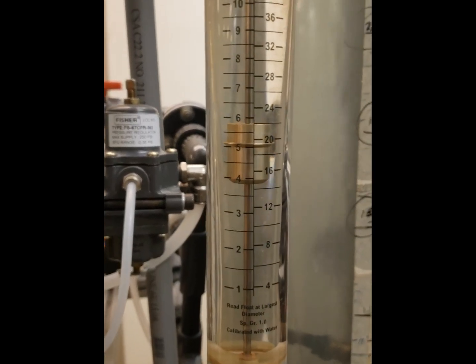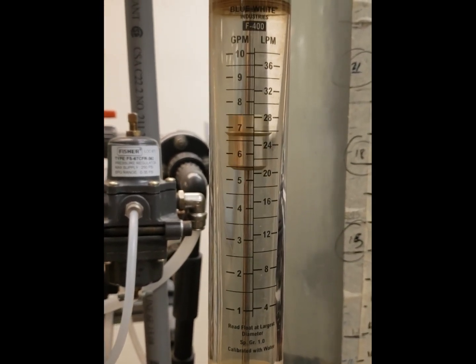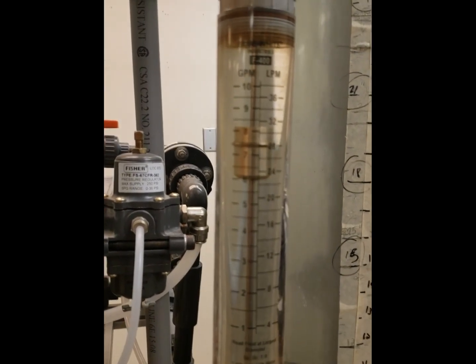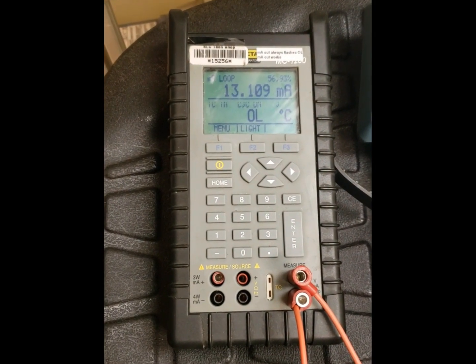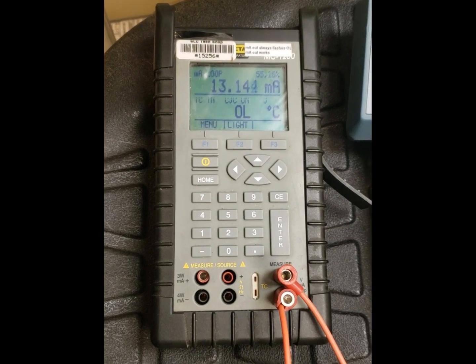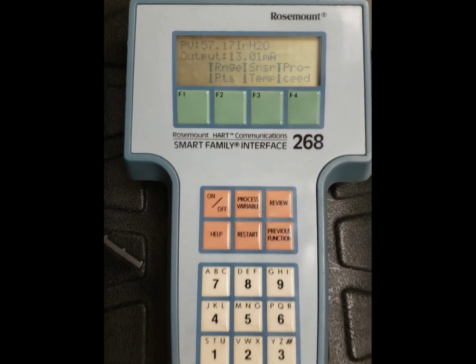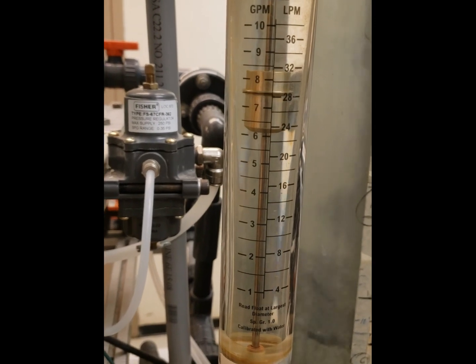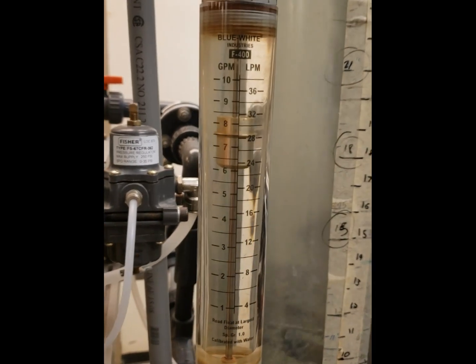So now we're going to go up and check out the seven point five. So at seven point five gallons per minute we are getting almost 50%, we're getting 13 milliamps. So now there's our differential pressure. So at 75% flow of our calibrated flow we are getting almost 50% output.